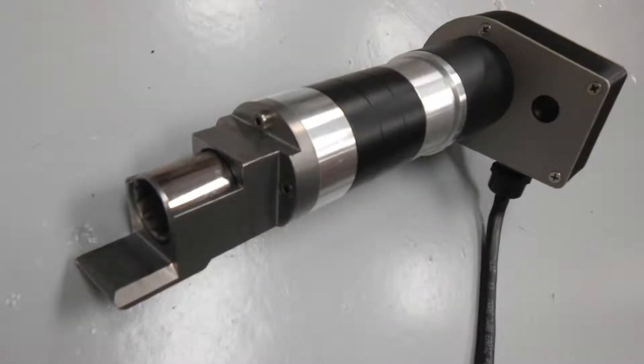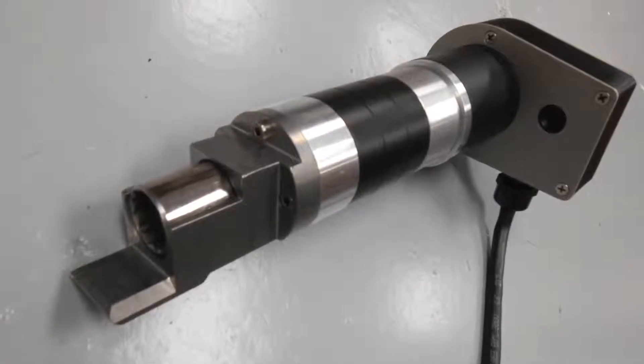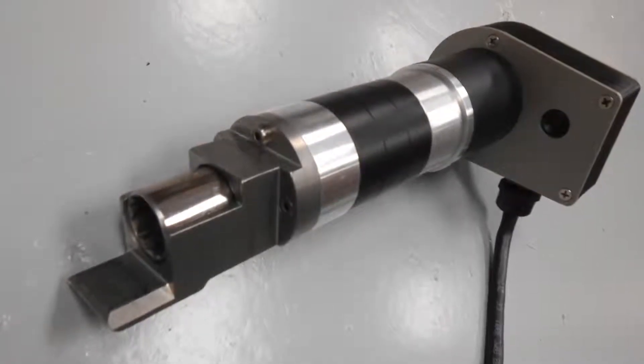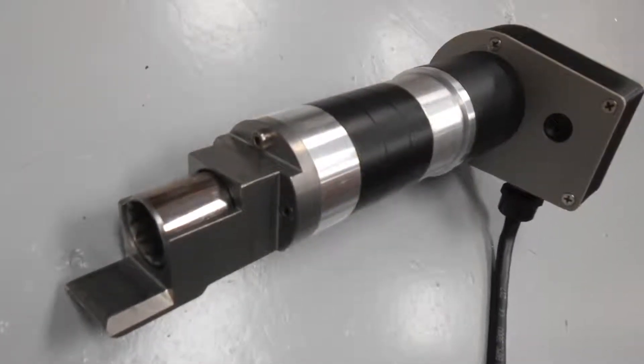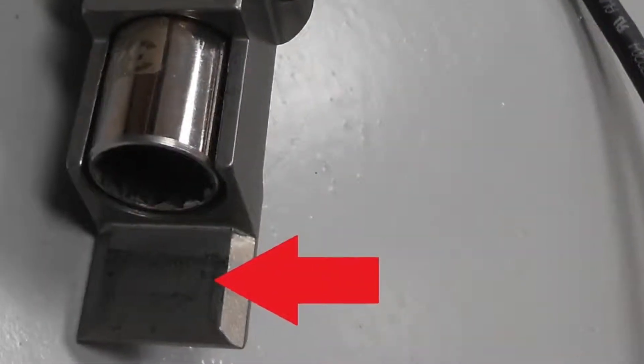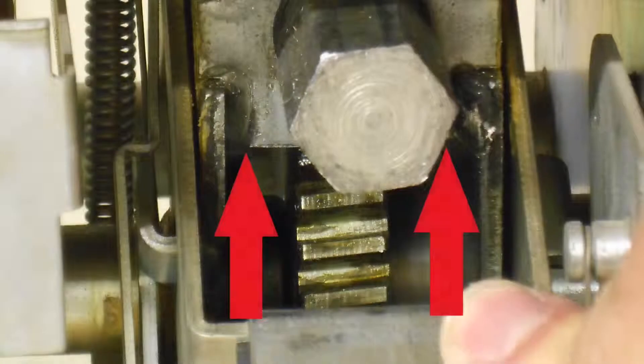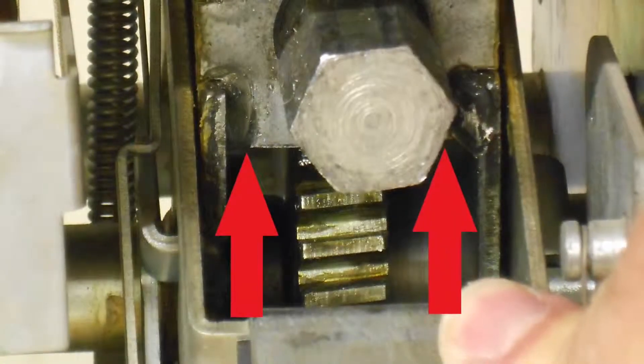The innovative design of the racking head is what really distinguishes the DSR-1 from other racking devices. The geometry of the racking head works in unison with the geometry of the breaker's racking mechanism. The tang on the racking head provides anti-torque for the racking motor. As the 12-point socket of the racking motor engages the racking nut, the tang slips underneath the support for the racking mechanism.